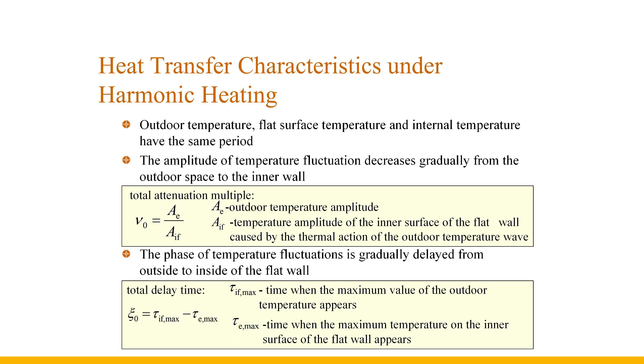However, the periodic thermal effects of the actual building envelope do not change according to the cosine function rule with time. When the calculation accuracy is not high, it can be considered approximately as a harmonic heating effect, taking the difference between the highest value of the actual temperature and the average value as amplitude, and determining the inner surface phase according to the time when the highest temperature value occurs.